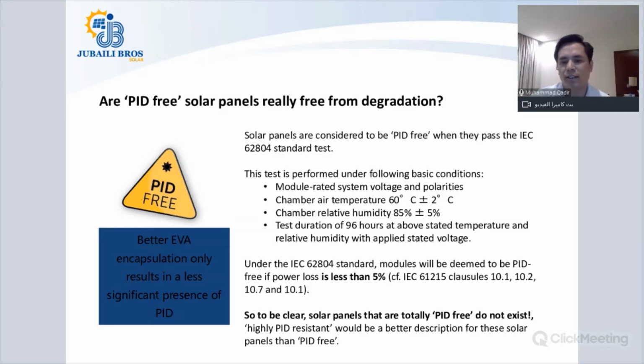So you guys would already be aware that there are many solar PV modules available in the market that say they are PID free. What is PID free actually, and how do they claim this? Actually, there is a certain IEC test, IEC 62804, that tests the solar PV modules and certifies the manufacturer's particular range of PV panel.